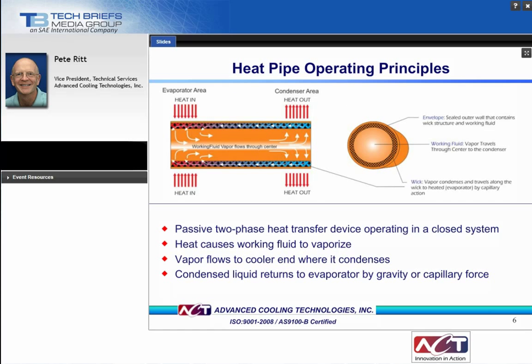Heat pipes are sealed vacuum devices. They are housed in a metal tube. Inside the tube is a wick structure and a small amount of a working fluid. Most applications are copper tube, copper mesh, and water, but there are several other envelope material, wick structure, and working fluid combinations. Heat pipes are passive two-phase heat transfer devices that operate in a closed system. To work, a heat pipe must be connected to a hot end or evaporator and a cold end or condenser, as can be seen in the schematic on the left.